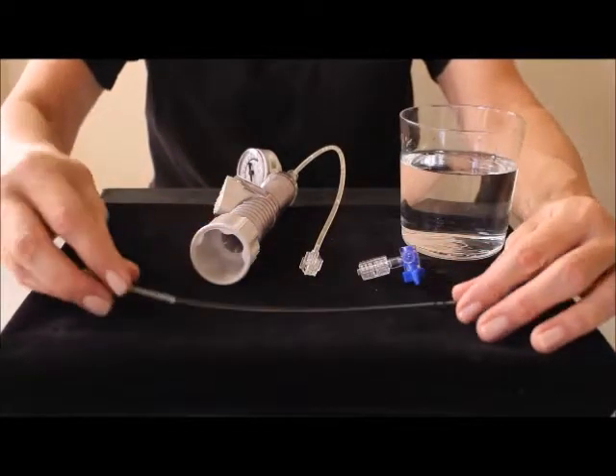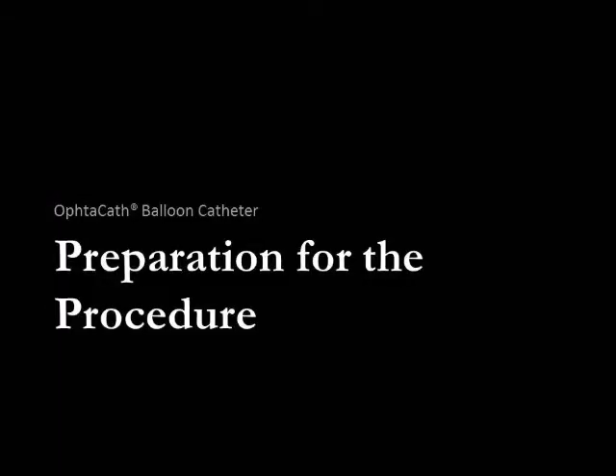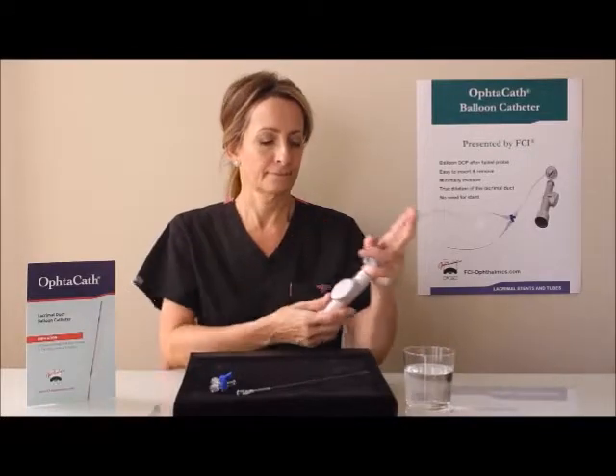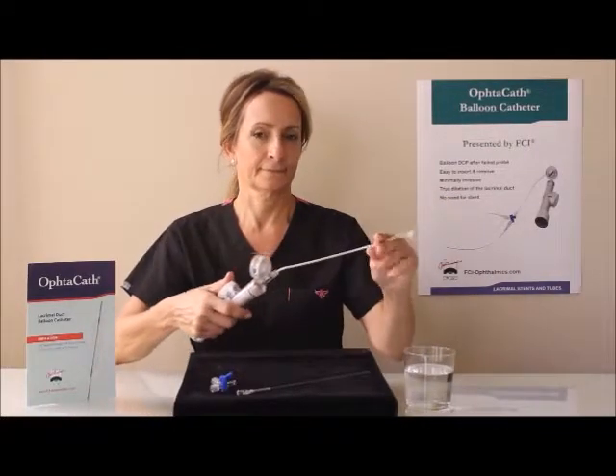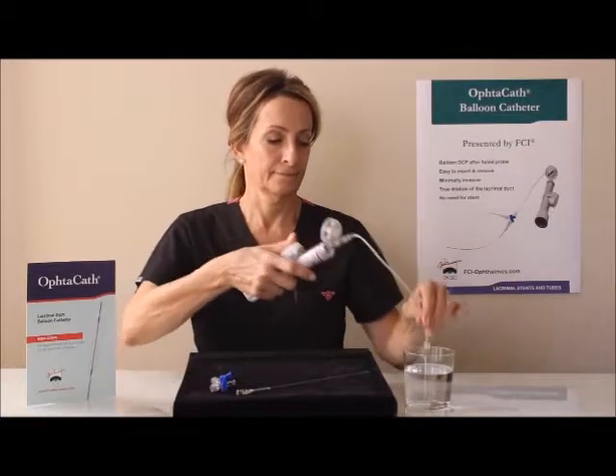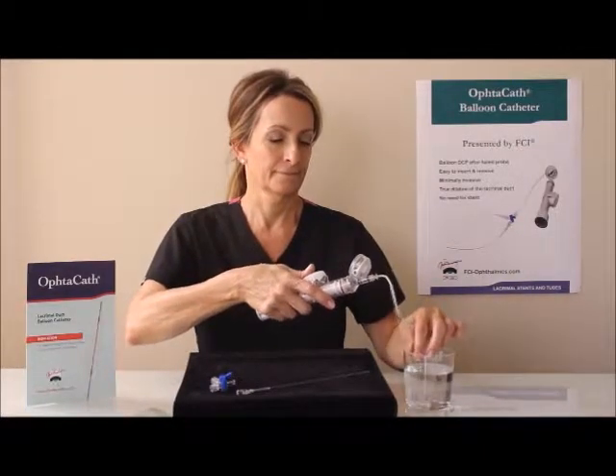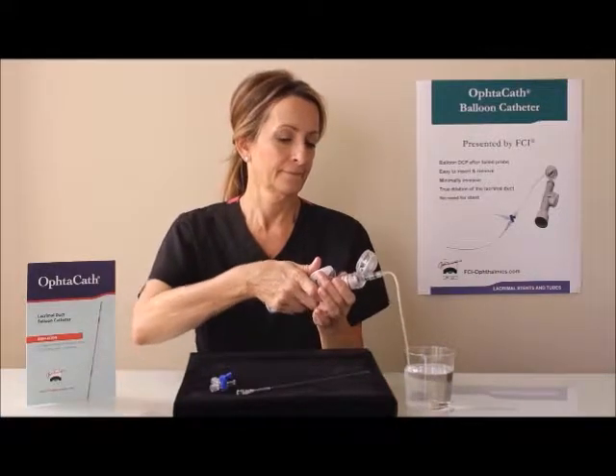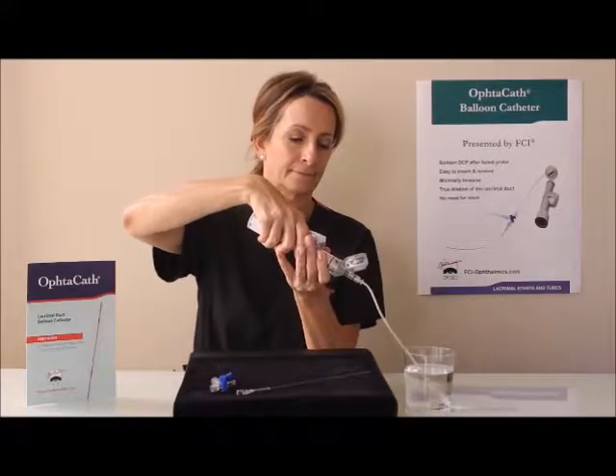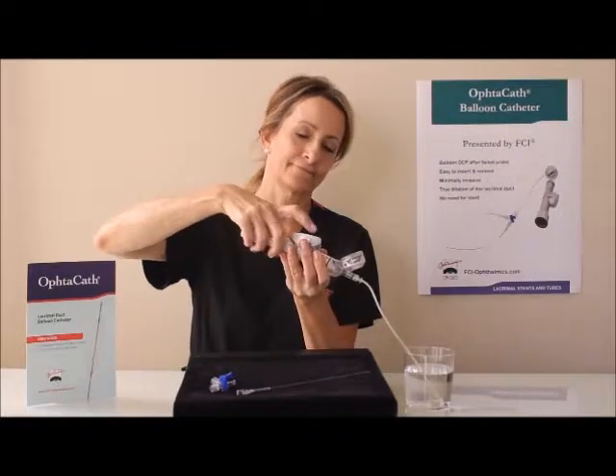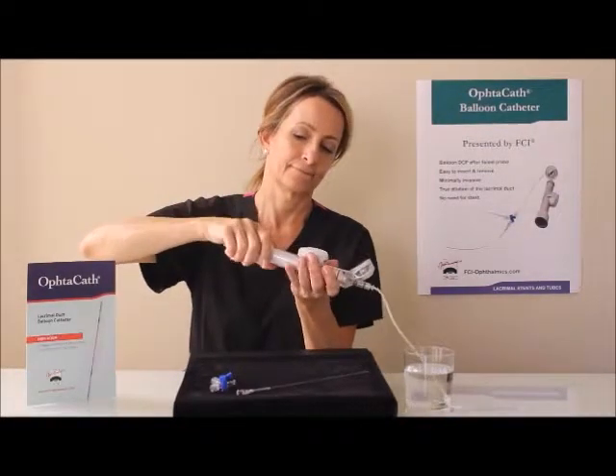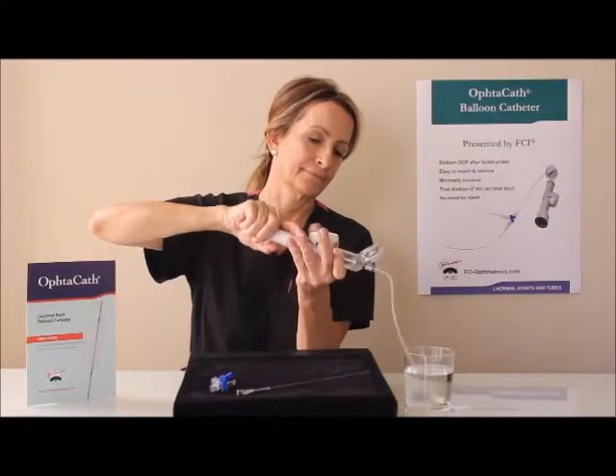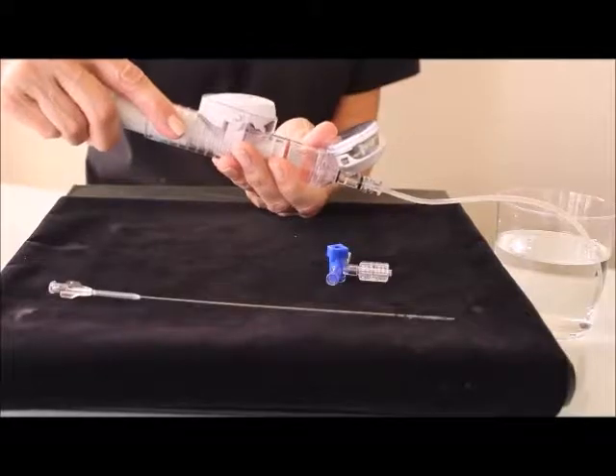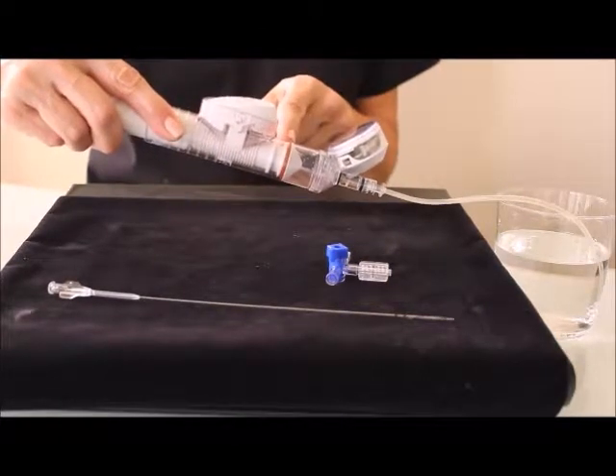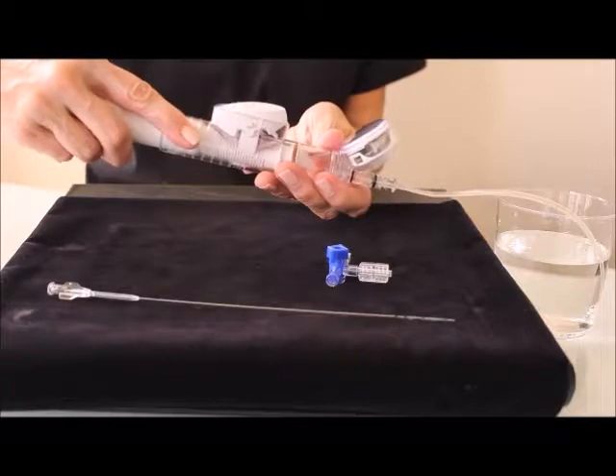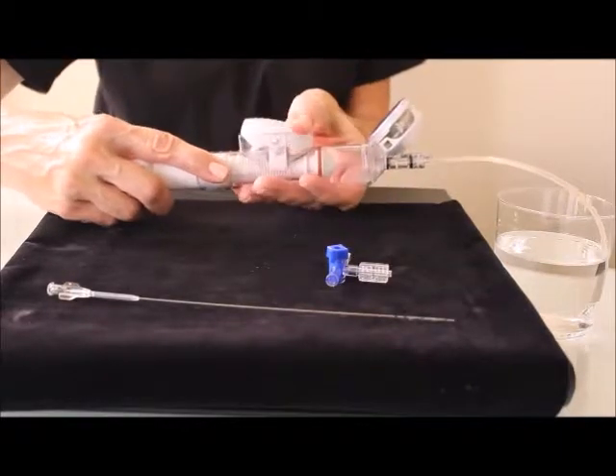Preparation for the procedure begins by unpacking the sterile inflation device and catheter onto the sterile field, and you will require a basin of sterile water or BSS. The inflation device control button is in the unlocked position and the device is pointing downward. At this time, you insert the end of the connector tube into the sterile water or saline to fill the syringe. Hold the device upward, purge the air contained in the syringe and connector, ensure that 10 cc's remains in the syringe, then lock the plunger by rocking the control button toward the manometer.